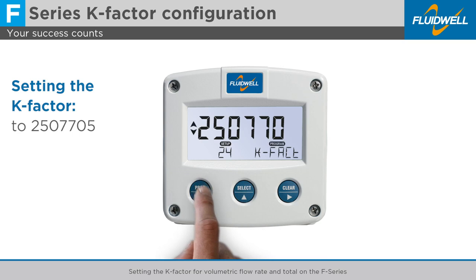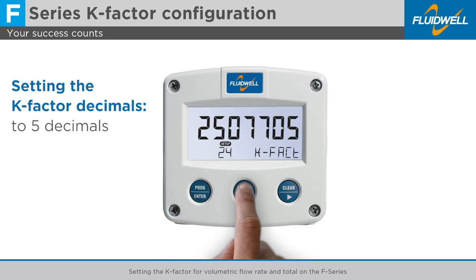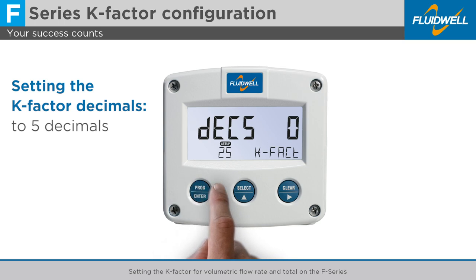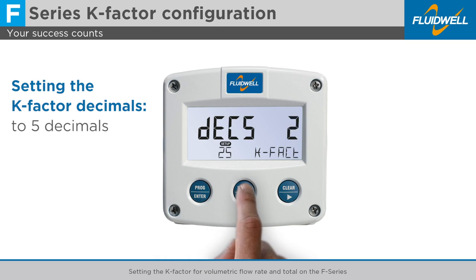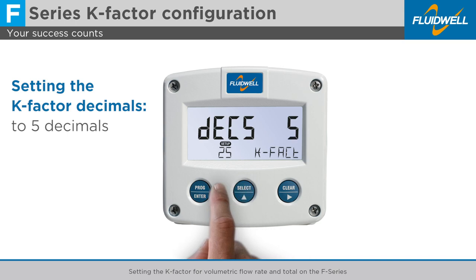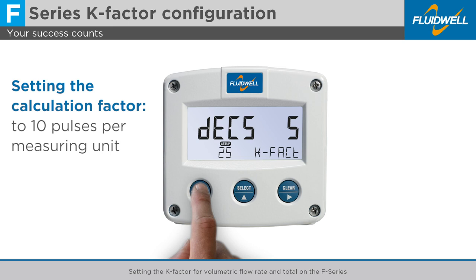Press Prog to store the K factor. Note that the amount of decimals is not set yet. Press Select to go to Menu 25, K factor decimals. Press Prog to set the K factor to 5 decimals. Press Prog to store this setting. Now the first part is configured, we are going to set a flow rate calculation factor next.